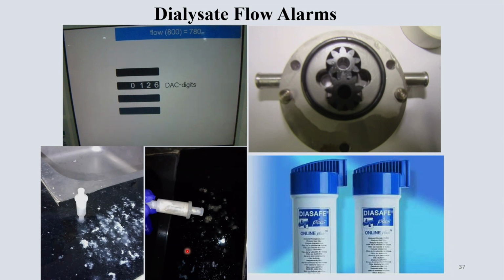We talked about how the Diasafe is guaranteed normally to have a life of 3 months or 100 treatments, whichever occurs earlier. And you can lose your Diasafe after the first treatment if precipitate of this sort is allowed to form. The second, on the right-hand upper corner, is the gear head of the machine. So all the pumps are geared pumps in the machine because they have to adapt the motor to the load for different dialysate flow rates.